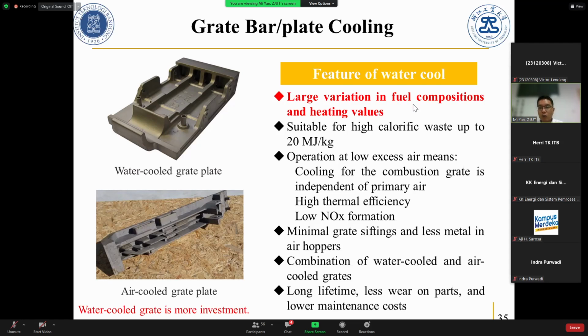The water cooling feature has many advantages, such as tolerance of large variation in fuel composition and heating values, and suitability for higher LHV, waste up to 20 megajoules per kilogram. For air cooling, that is impossible. Another advantage is operation at low excess air, because if you use air cooling, your primary air depends not only on the combustion requirement but also on the cooling requirement. So you just do a balance. You cannot control the excess air very well.